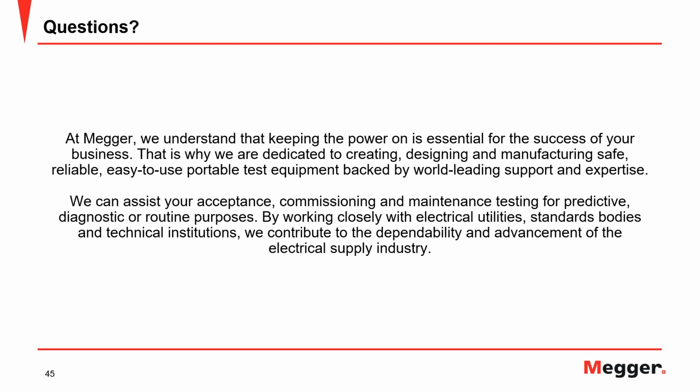Thank you, Sanket. Next to Diego. Does NBDFR provide insight in capacitance changes in bushings, or is it restricted to % power factor? That is an excellent question, and thank you for asking that. We focus right now on the sequence of power factor from the line frequency value to narrowband having 1 to 500, and from full DFR going from 1 millihertz all the way to 1 kilohertz.